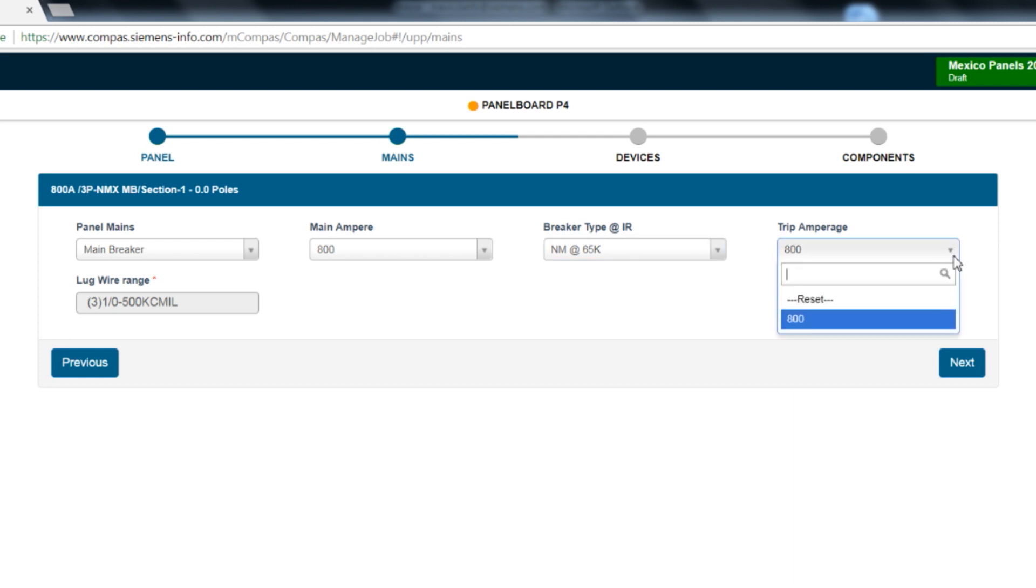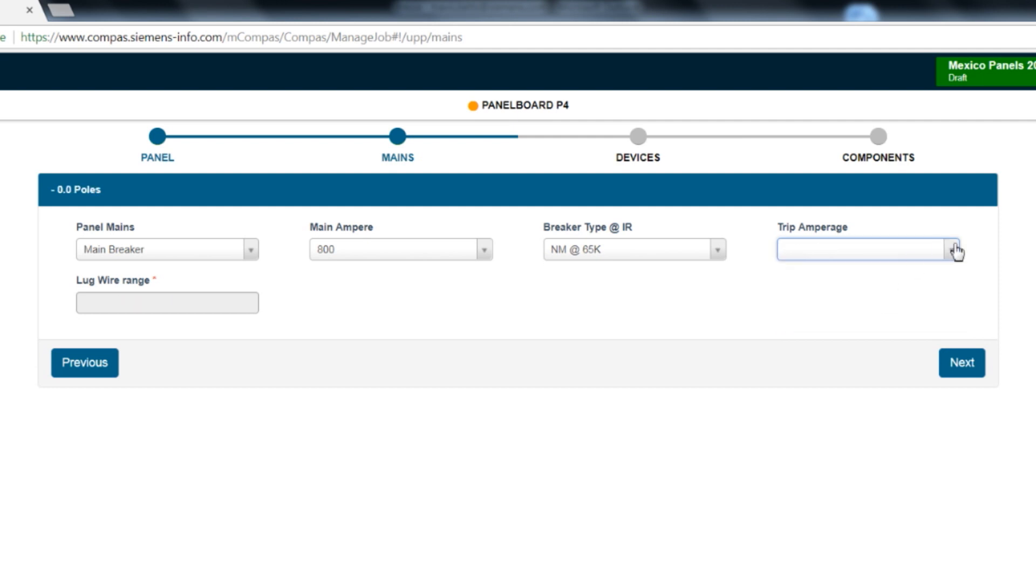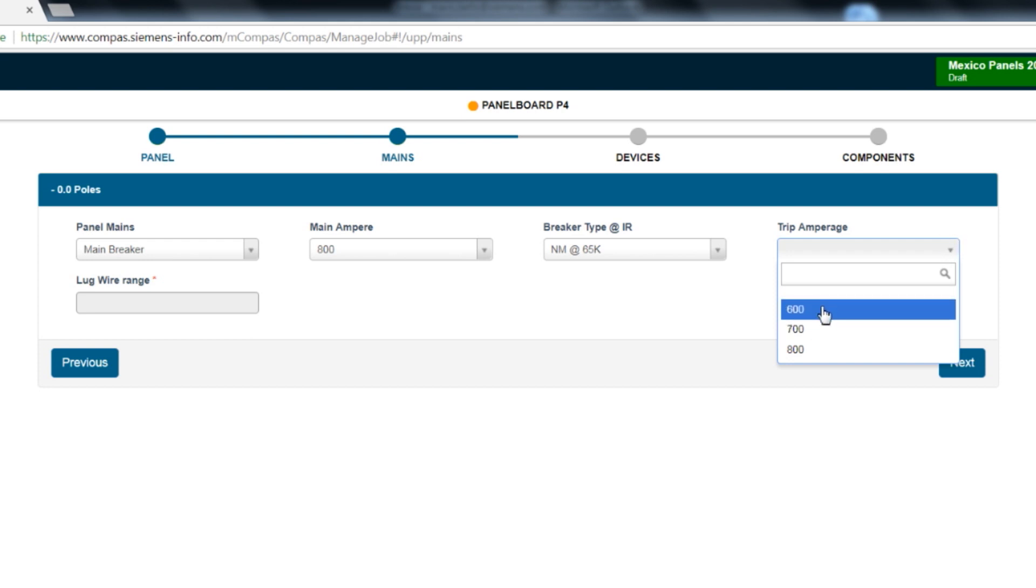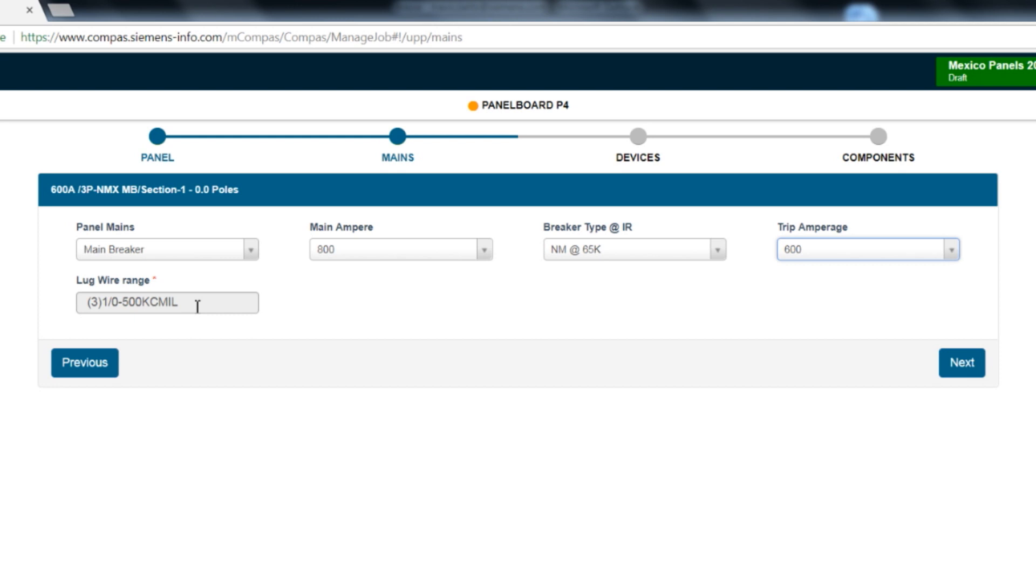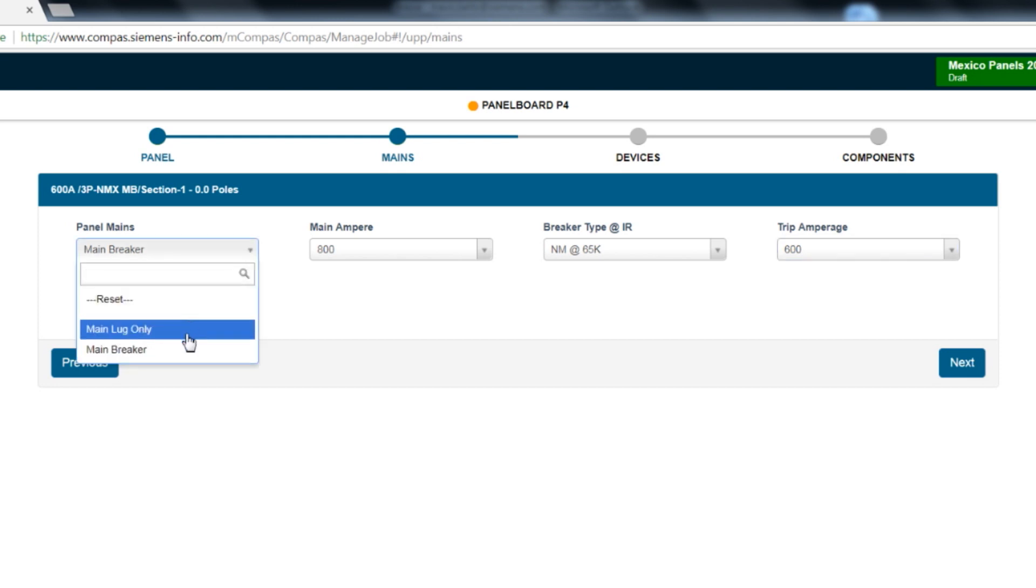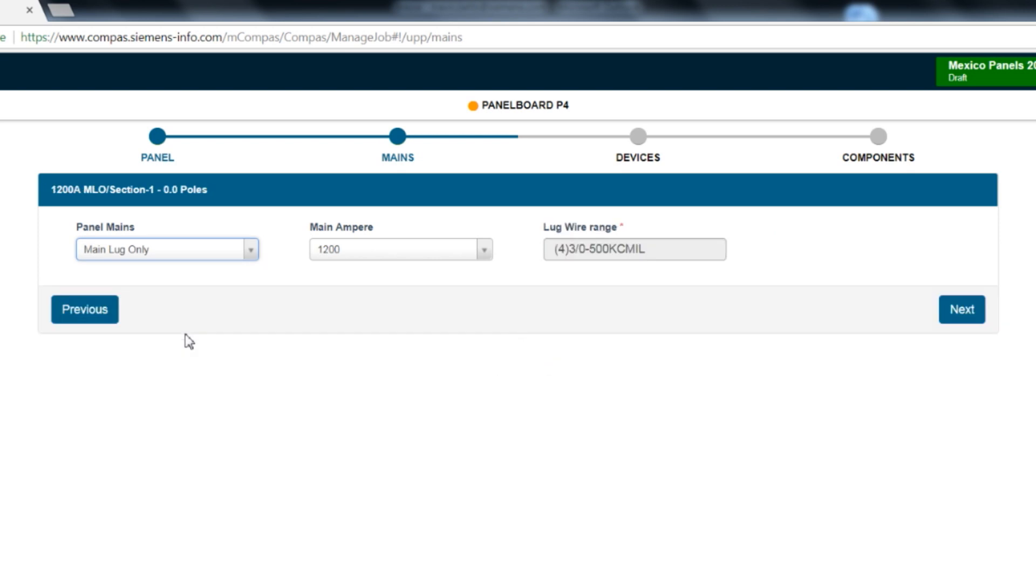Finally, the last option is trip amperage. The default selection matches the frame amperage. If you hit reset, you can select all available frame amperages for the main amperage breaker. If you adjust the trip amperage, you may need to reselect breaker type. On this page, it will also show the wire range of the selected main. For this example, we will select the 1200 amp main lug option.